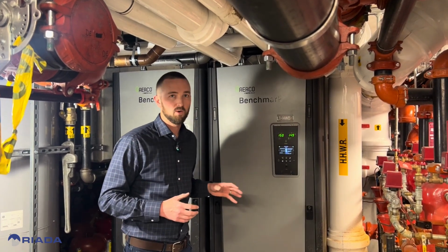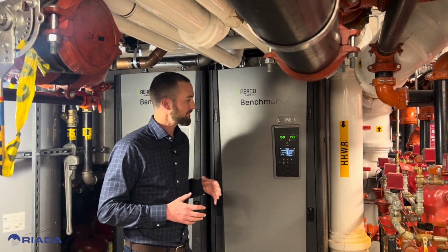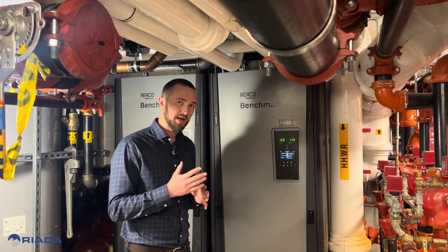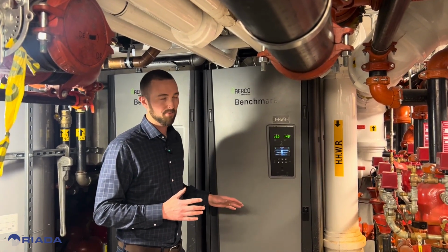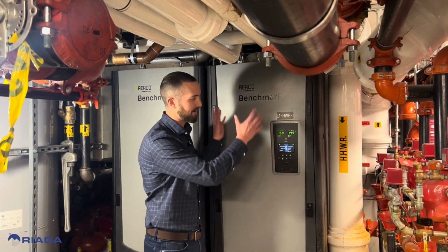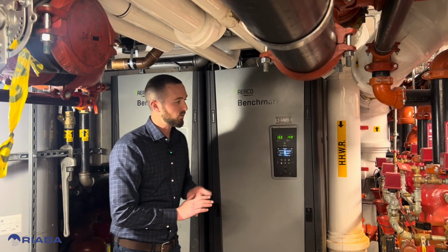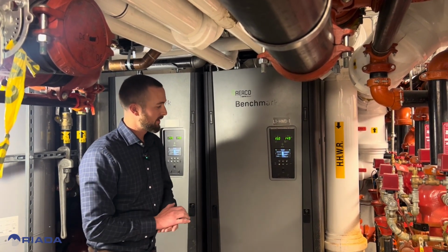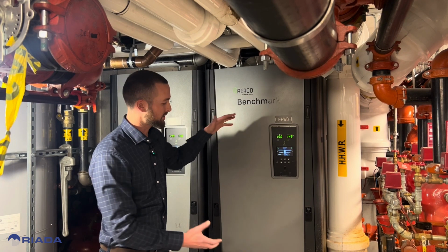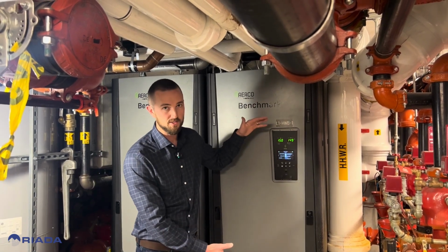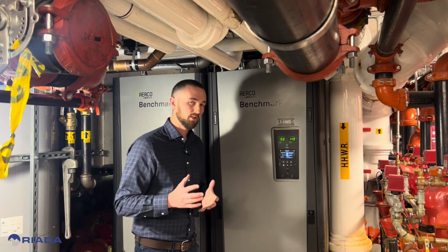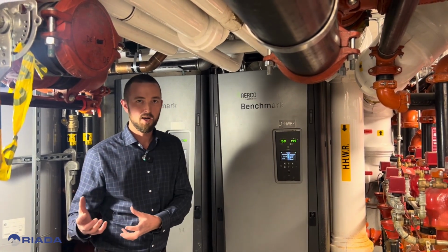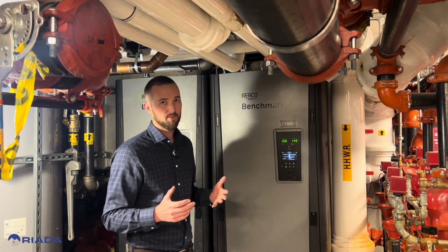How AERCO can help with seasonal efficiency, for a number of reasons. First of all, they design and manufacture their own gas valve in-house at the factory. What this means is we can do a very high turndown through a single heat exchanger. So each boiler, these are not modular boilers, they have one heat exchanger with a single downward firing pass of the flue gases. And with all that square footage of heat exchanger surface area, at low fire, we get a very high heat exchanger area to firing rate ratio. And that's great for efficiency. We call that seasonal efficiency.